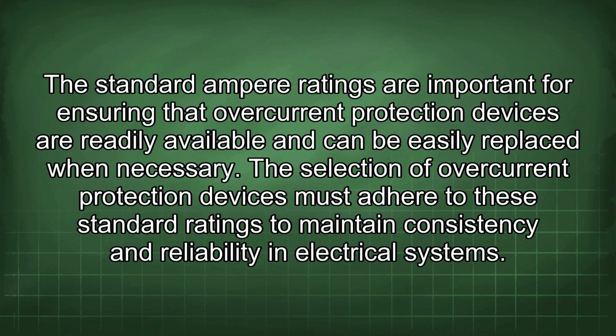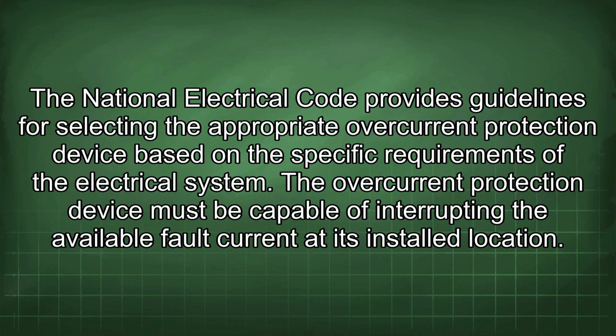The standard ampere ratings are important for ensuring that overcurrent protection devices are readily available and can be easily replaced when necessary. The selection of overcurrent protection devices must adhere to these standard ratings to maintain consistency and reliability in electrical systems. The National Electrical Code provides guidelines for selecting the appropriate overcurrent protection device based on the specific requirements of the electrical system.